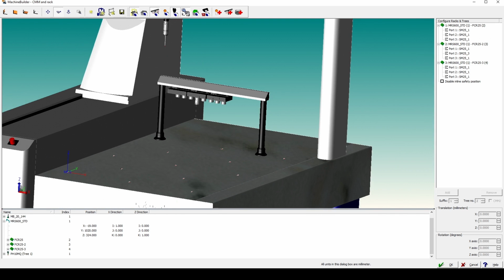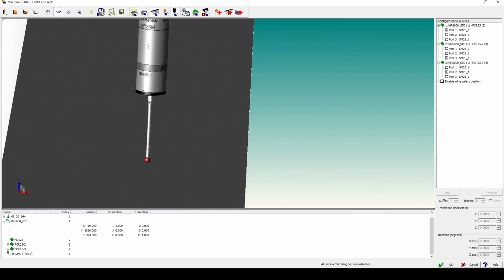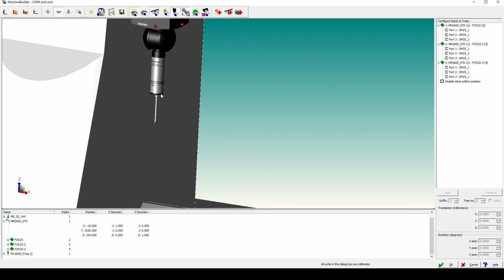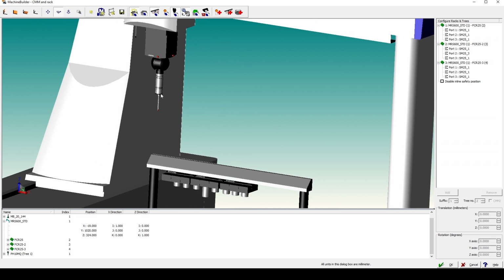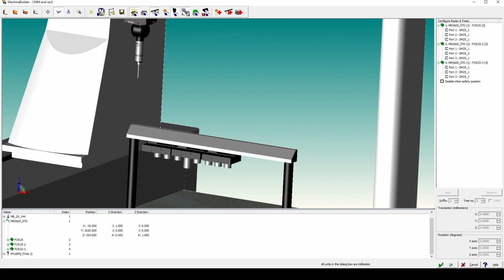And this FCR25, you can configure it to hold only SM25 or SH25, the black stuff. This is the probe holder, and you cannot configure it to hold both of them.